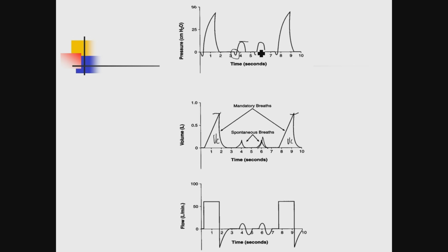In most cases, you'll probably get a pretty close tidal volume each time, because compliance and resistance aren't changing on a breath-by-breath basis typically. Over time, though, yeah, not in that short time frame. How do I know it's also volume control? I'm fixing the inspiratory flow rate. I know I'm throwing around a lot of information here. Bear with me. We'll walk through it in the lab one by one.